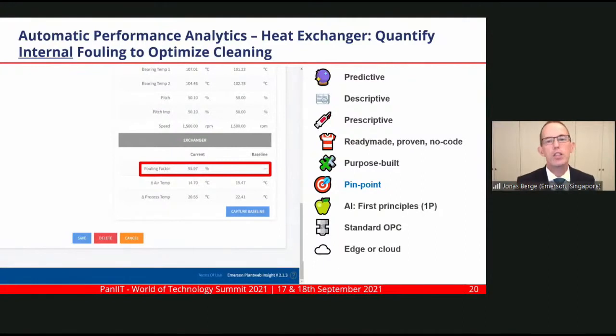So again, plants are automating this - they put in additional sensors and software. With that, through the software, you can tell what fouling is happening inside, let's say, the heat exchanger, because you have the fouling factor there. Based on that, you know whether you need to clean the heat exchanger today, or can wait until the next turnaround, or do it sometime in between when convenient. And if the heat exchanger has multiple bundles, a bank of multiple bundles, it pinpoints which bundle you need to clean, so you can bypass and clean just that bundle rather than the entire heat exchanger.